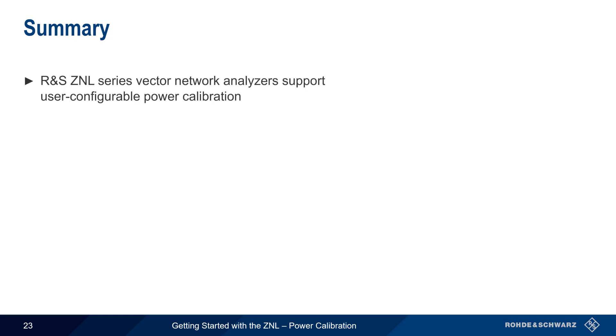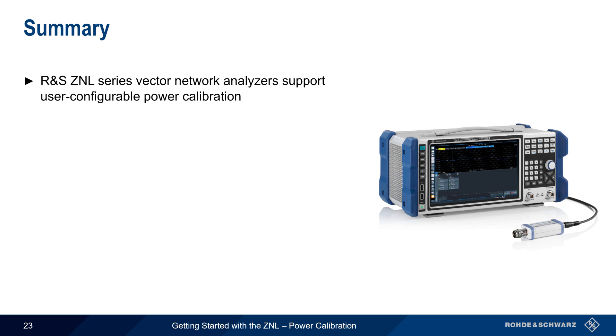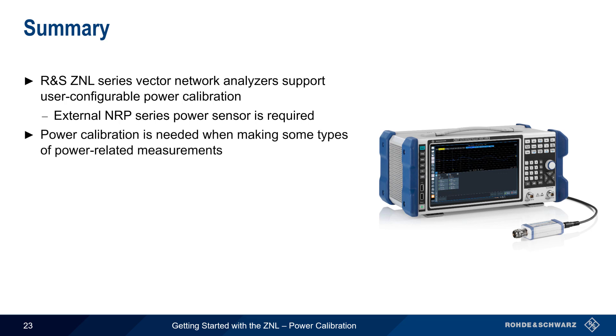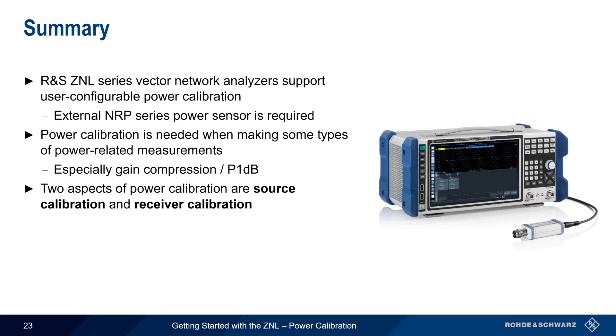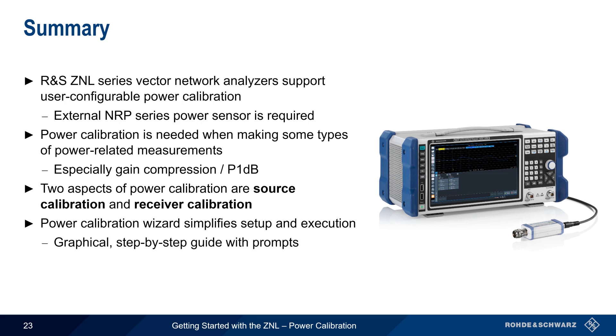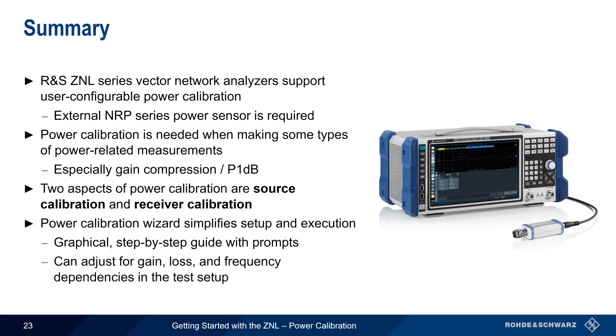Let's end with a brief summary. Rohde & Schwarz ZNL Series Vector Network Analyzers support user-configurable power calibration, typically performed using an attached NRP Series power sensor. Power calibration is needed when making some types of power-related measurements, in particular when measuring gain compression or P1dB. The ZNL supports both aspects of power calibration: source calibration and receiver calibration. The ZNL's Power Calibration Wizard makes it easy to set up, configure, and run calibration. A graphical step-by-step guide prompts the user through the process, and power calibration configuration can also be adjusted to account for gain, loss, or frequency-dependent behavior in the test setup. This concludes our presentation, Getting Started with ZNL Power Calibration. For more information about power calibration, power-related measurements, or vector network analyzers from Rohde & Schwarz, please see the links in the video description.